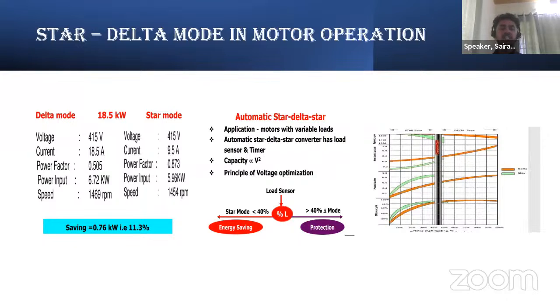By this energy conservation method, we will be getting an energy savings of around 10 percent. As mentioned here, in an 18.5 kilowatt motor, after converting from delta mode to star mode, we have got an energy savings of around 11.3 percent.